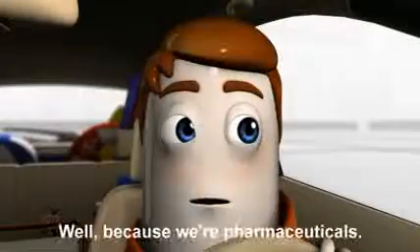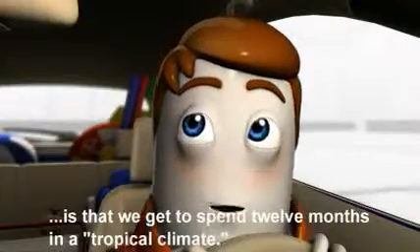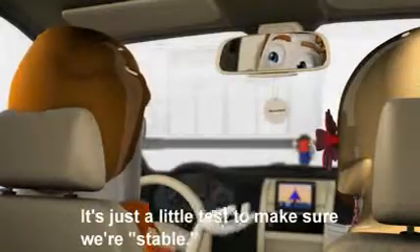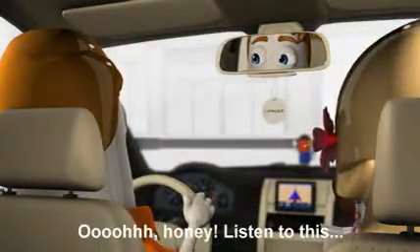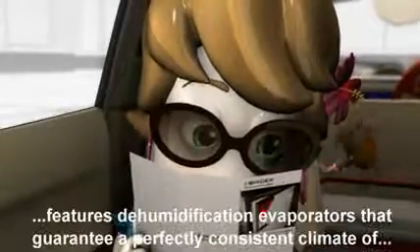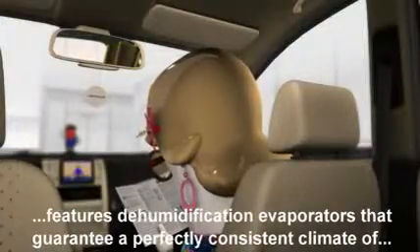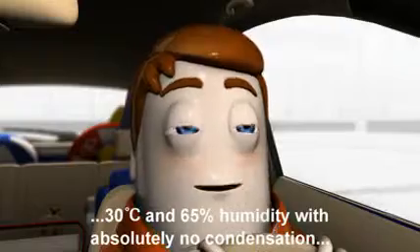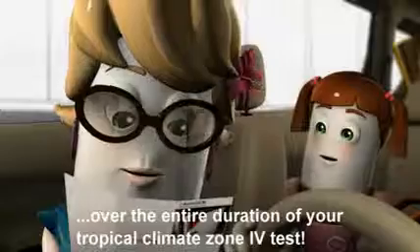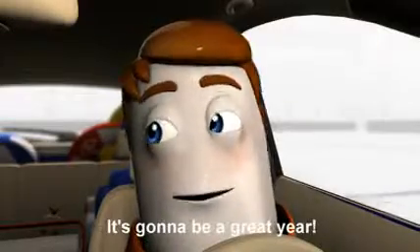Why are we going? Well, because we're pharmaceuticals, and one of the great things about being pharmaceuticals is that we get to spend 12 months in a tropical climate. It's just a little test to make sure we're stable. Ooh, honey, listen to this. The Binder KBF Stability Test Chamber features dehumidification evaporators that guarantee a perfectly consistent climate of 30 degrees Celsius and 65% humidity with absolutely no condensation over the entire duration of your Tropical Climate Zone 4 test.